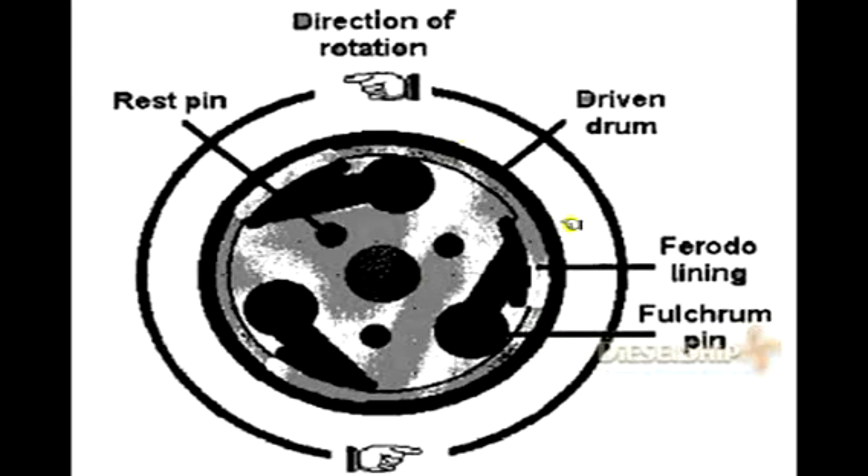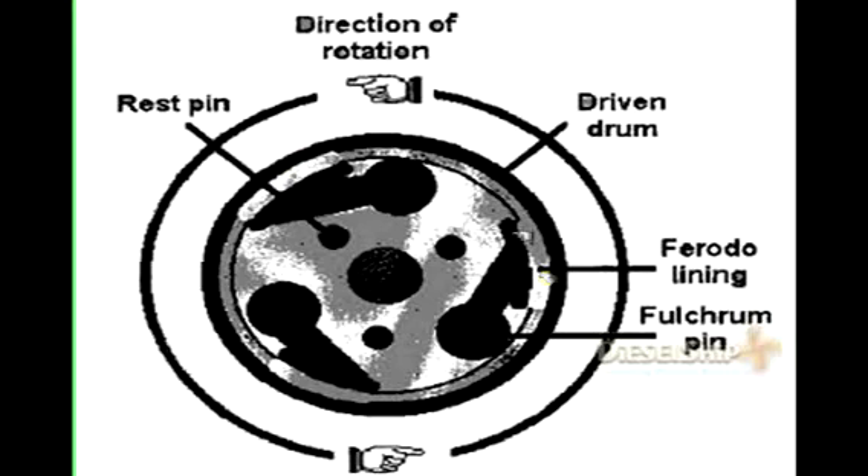Next, let's discuss the centrifugal clutch and its arrangement — specifically the friction drum. The picture shows the inside view of the friction drum. There is a central hole through which the horizontal shaft passes. Three fulcrum pins are mounted upon which the clutch pads are attached; the number of pads depends on the manufacturer and shaft speed, and may vary from two to eight pads. We also have rest pins upon which the pads rest when the purifier is stopped. Each pad has a rubber lining on its shoe, commonly called ferrodo lining, named after the famous company that manufactures it.